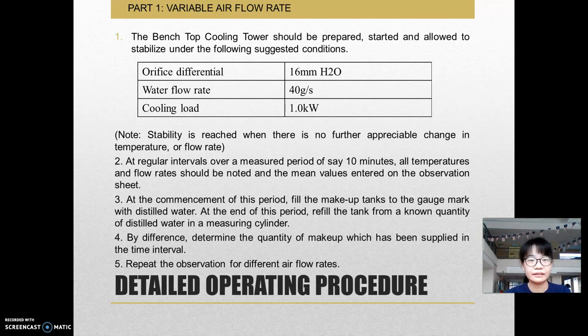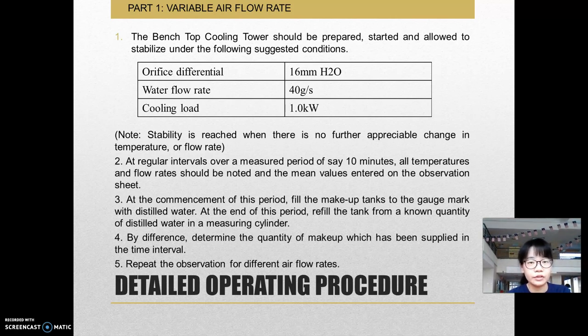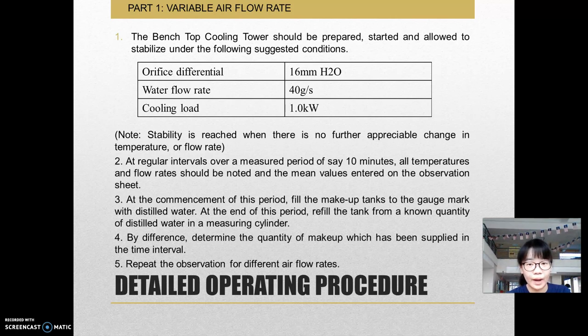The experiment is conducted and divided into three parts. For Part 1, it is related to variable airflow. For the operating procedure, firstly, the bench top cooling tower should be stabilized under the suggested cooling conditions — for example, the orifice, the heater settings. For water flow rate, it should be adjusted to 40 grams per second, and the cooling heater should be adjusted to 1 kW.